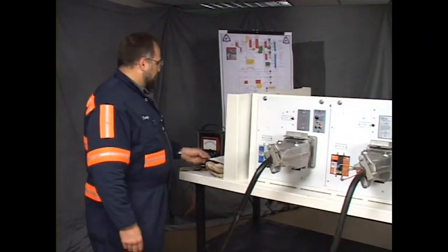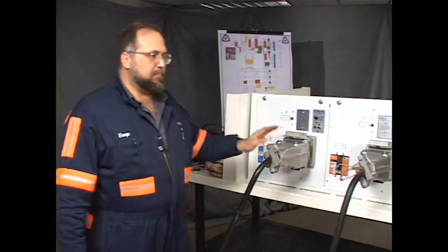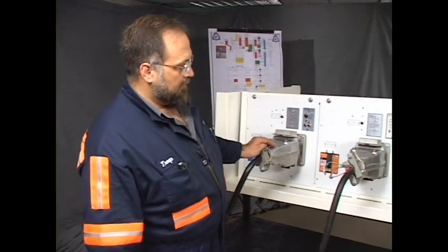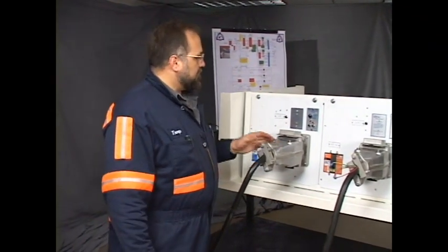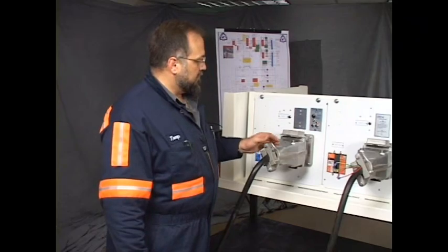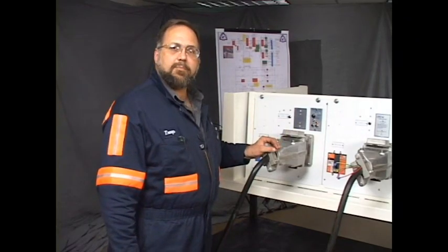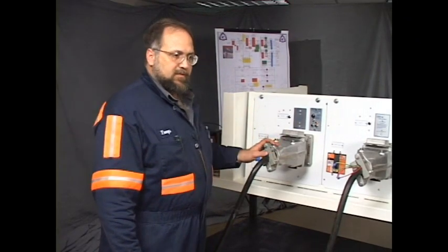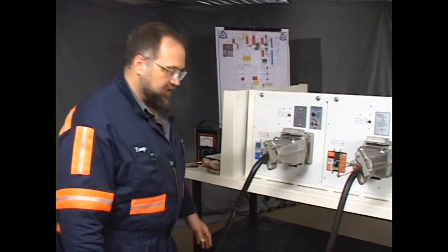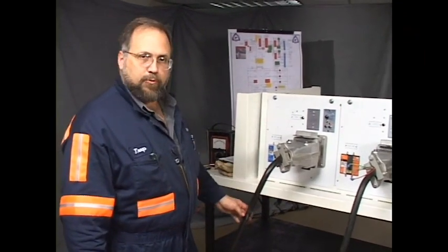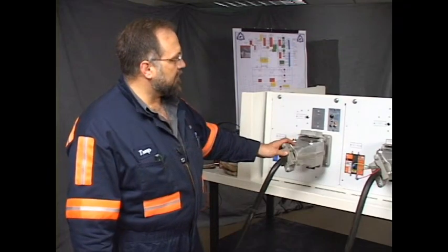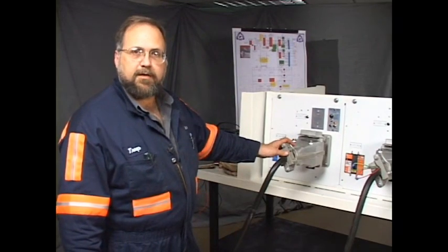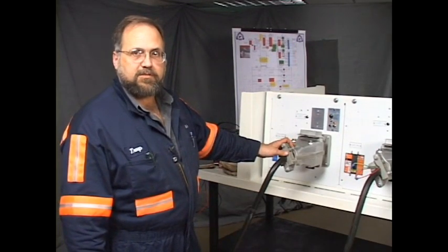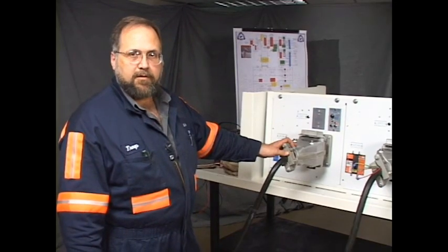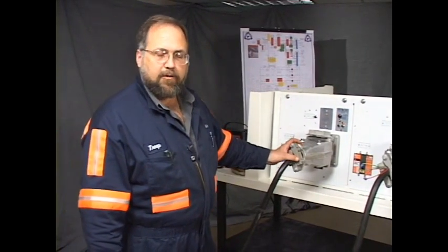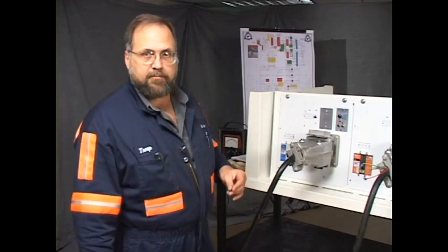The troubleshooting that we've done on the prior circuits involved an impedance type monitor. In the impedance monitor, you have a reference voltage between the ground pin and the pilot pin, and that circuit is extended all the way to the machine. As long as that loop is intact, the monitor is satisfied and it will close a relay. That's the GCS 1 contact between 3 and 1, and allow power to be put to the UV.